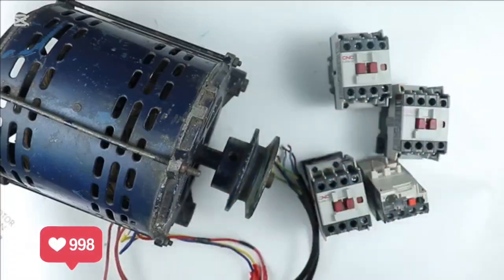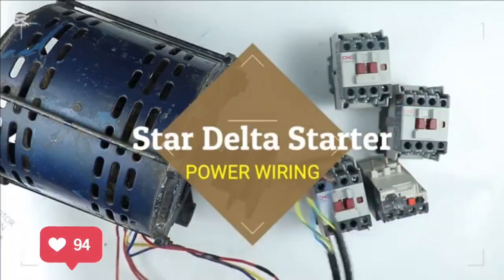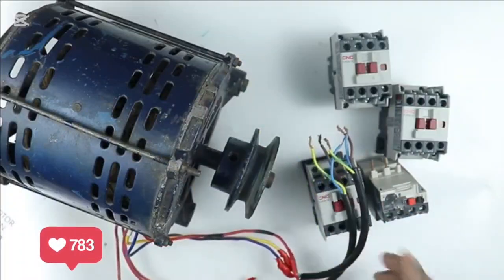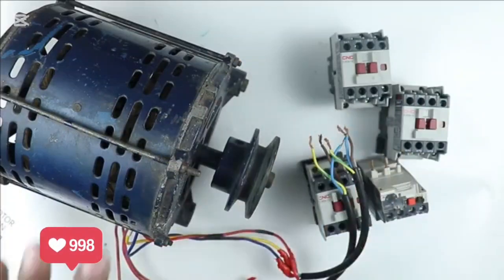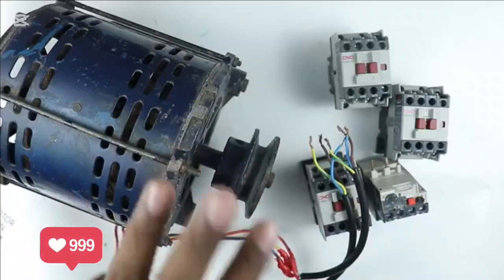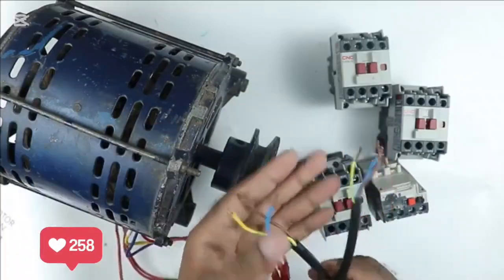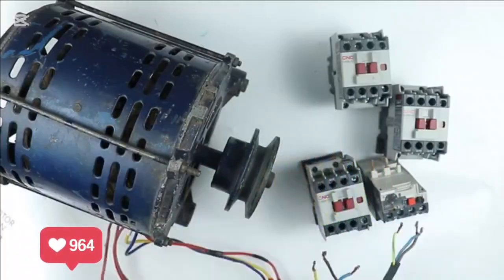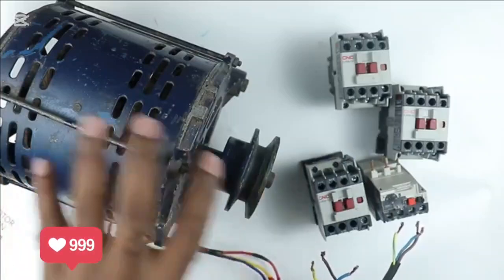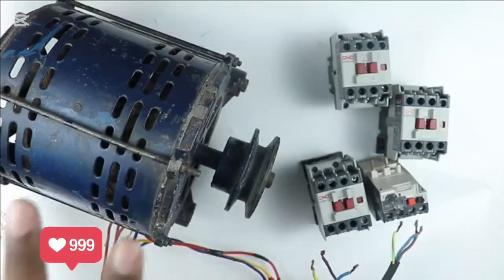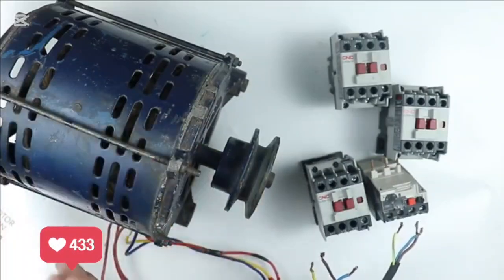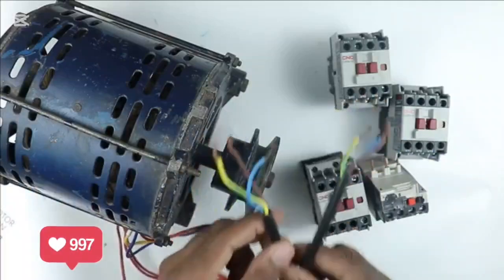So today in this video, we are going to learn how to do the power wiring of a star delta starter with every basic detail. Like I told you, I have this 3-phase motor, and inside it a total of 3 windings are present, and from these 3 windings a total of 6 wires come out for connection. Normally the wires are connected to the terminal box of the motor, but the motor I have now has no terminal box. The wires come out directly from the windings.